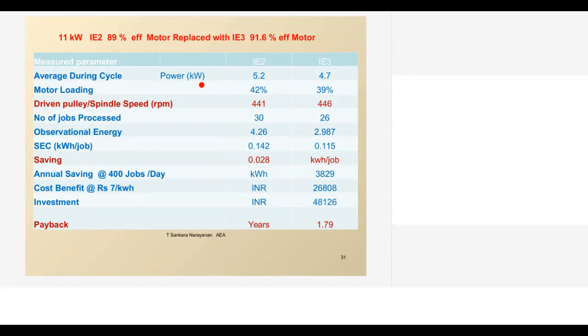So the average duty cycle power is taken. IE2 was taking 5.2 kilowatt, IE3 was taking 4.7. Then the motor loading: in the case of IE2 it is 42%, IE3 39%. Once you have seen the motor loading, there is an opportunity not to replace with the same 11 kilowatt. We could have reduced to a 7.5 kilowatt motor, but the industry, because they are starting with IE3 motors, told us they will replace with the same capacity. Otherwise, going by the loading, this operation can be done with a smaller motor rating. But as per the industry request, the same 11 kilowatt was replaced.